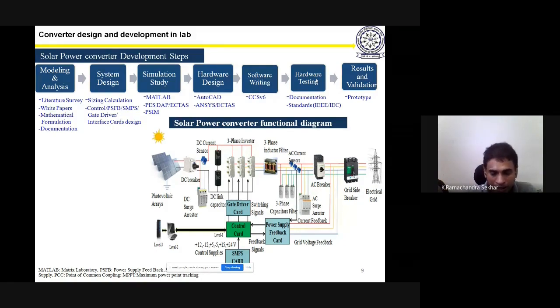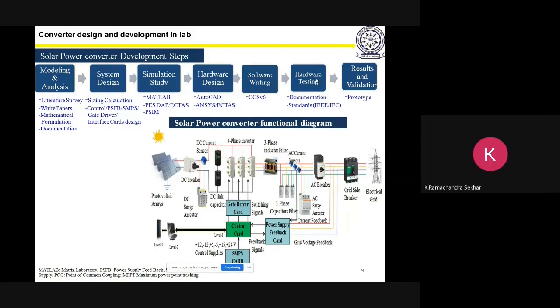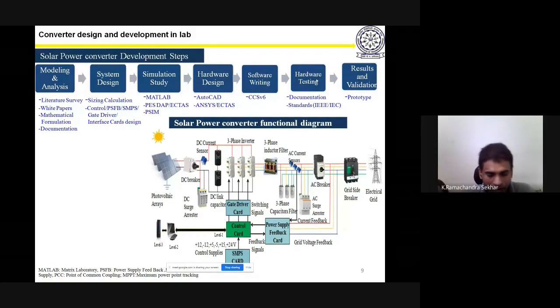So that breaker, the government of India recently has come up with certain requirements. As a manufacturer, what I will do is immediately isolate my system from the grid, because I don't want to spoil my system by supplying more current. Of course, because it's not capable, but the capacitor I have to actually supply that much reactive power. As a manufacturer, I don't want to size my capacitor to that level so I can reduce my price. That's the reason I won't bother about the LVRT issues.